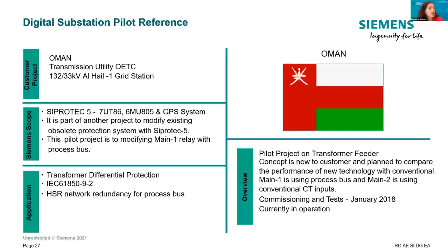Finally, I'll talk about an example of a reference we have in Oman: Al Hail, a grid station where we installed an LPIT to convert the station into a digital substation, also with process bus. This was done a few years ago and is currently in operation with much more efficiency in the process, which allows for better maintenance and so on.